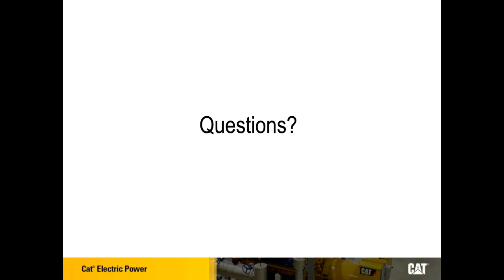Can you parallel a diesel with a gas genset? It's something we've been addressing a lot lately, specifically with some of the large hurricanes that came through, where the issue of getting fuel into sites became a problem. We have some hospital applications, specifically in Florida and other parts of the country, that have a diesel generator set to pick up the 10-second load, but also have natural gas generator sets there to extend run time during a long outage. We are able to parallel those gen sets together. There are a few additional steps needed to parallel the natural gas with the diesel generator sets, but it's something we do fairly commonly. In applications like a hospital, where you need to be prepared for an extended outage, it's something we've seen a lot of questions about lately, and we can certainly help with that.